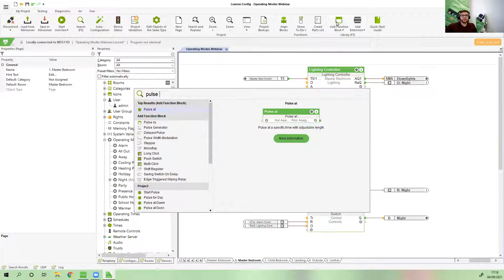In live view, you can see here that night mode is active, which means that the reset is held on, which means that I physically cannot do anything with this lighting. You would have just locked all of the lighting in your entire house, and the lights would not be able to turn on. Not through a switch, not through the app, not through nothing. Reset is dominant. So you shouldn't have these operating modes directly on resets.